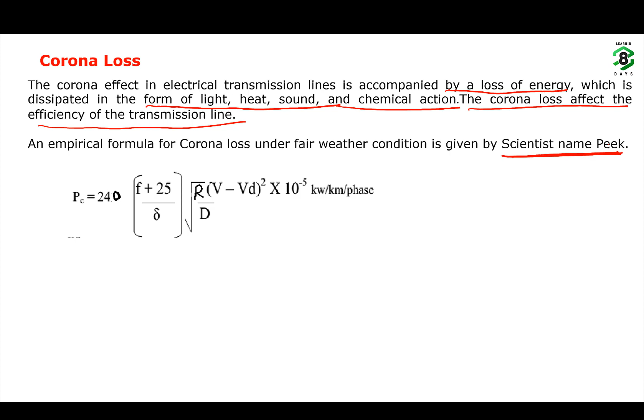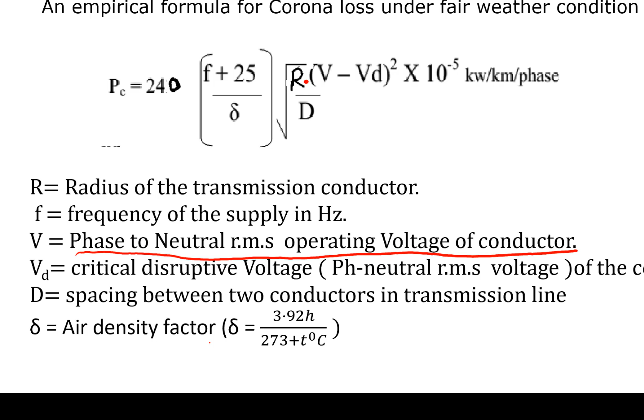A scientist called Peek has given an empirical formula to calculate the corona loss. Corona loss is given by 240 into (f plus 25) divided by delta, into the square root of r by D, into (V minus Vd) squared, into 10 to the power of minus 5 kilowatt per kilometer per phase. Here, r is the radius of the transmission conductor, f is the frequency in hertz, V is the phase to neutral RMS operating voltage, Vd is the critical disruptive voltage, D is the spacing between the conductors, and delta is the air density factor.